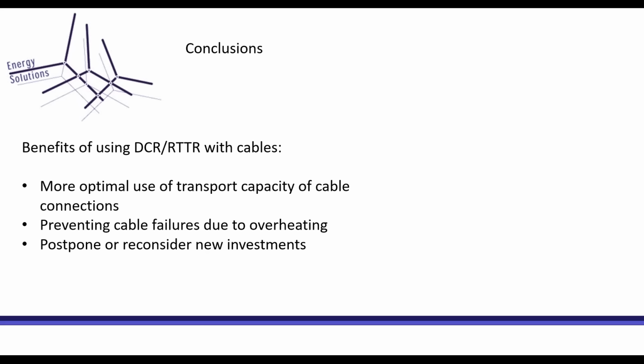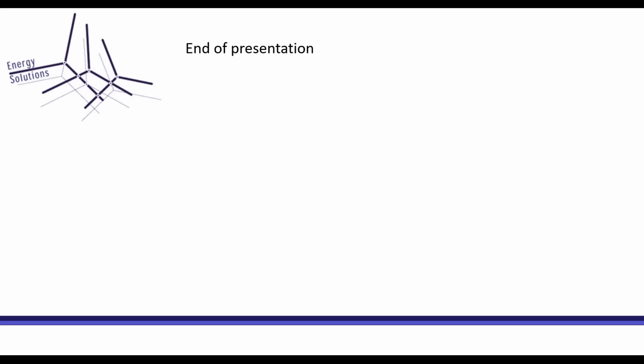Heating. And yeah, in that case, when you have some problems in the grid, or you expect some problems in the grid, but you measure it and there will be no problem, then you can postpone or reconsider your new investments. Really, the biggest bottlenecks that we have seen is with the offshore wind, but more recently there's also the big solar farms that can give some problems due to the high peaks during the afternoon. So that's basically the presentation about dynamic cable rating.